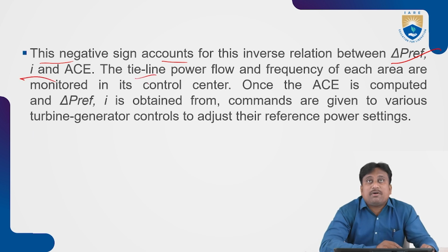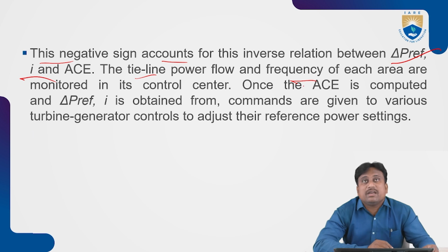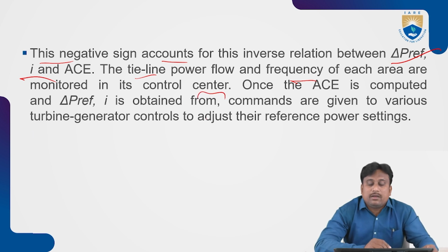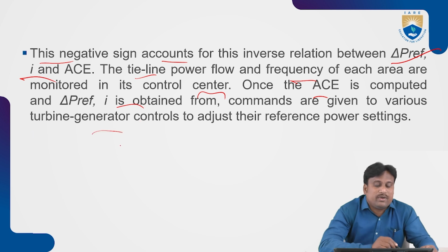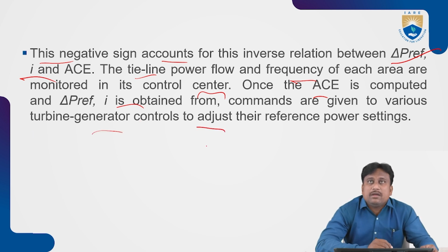So that tie line power flow and the frequency of each area are going to be controlled in the control center. Once the area control error is calculated, delta P reference i is obtained from the commands which are given to various turbine generator controls. They are ready to adjust their reference power settings to the required values.